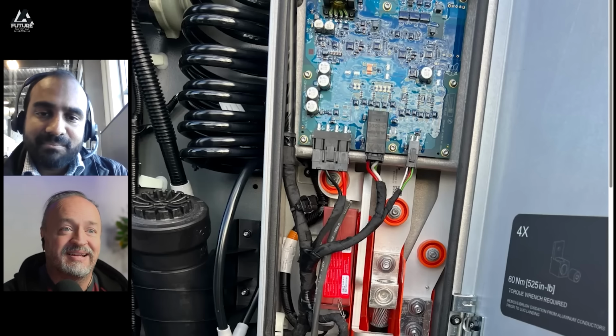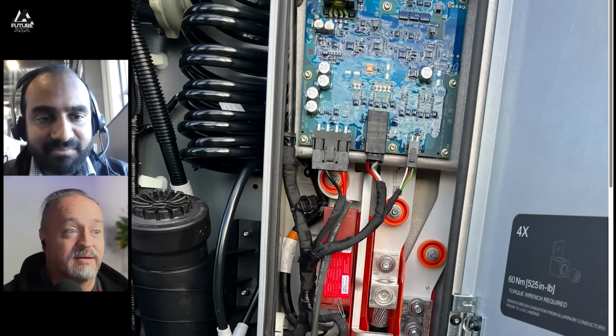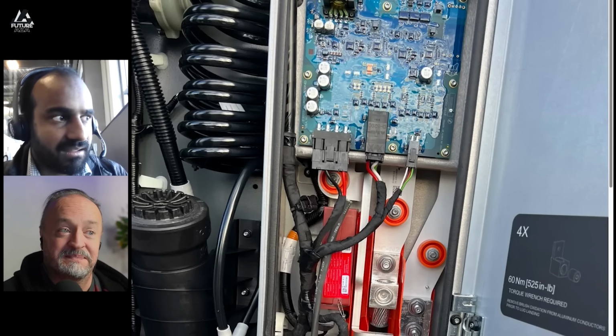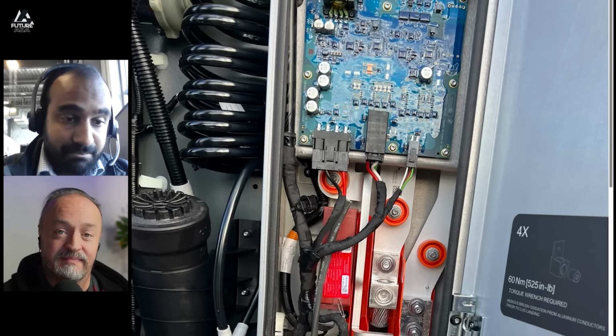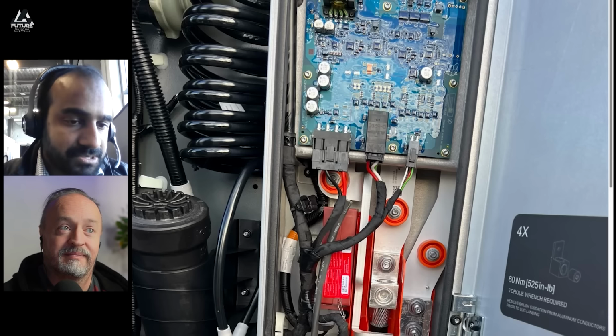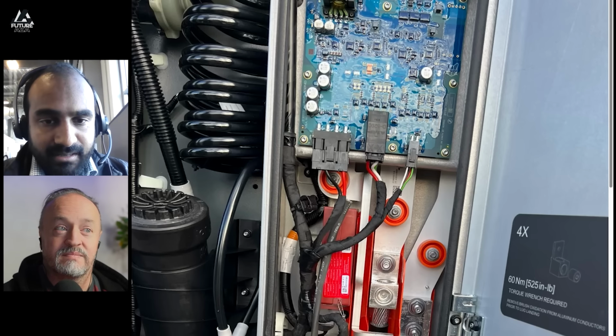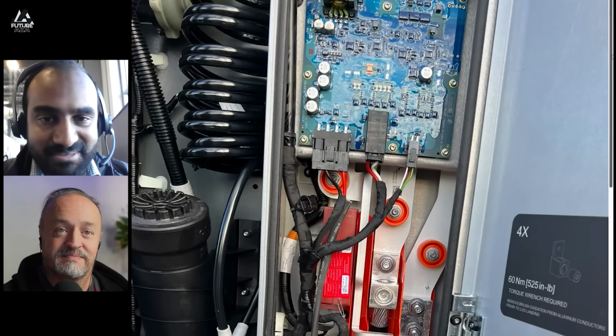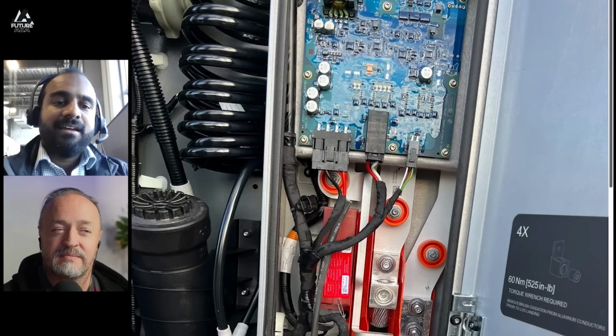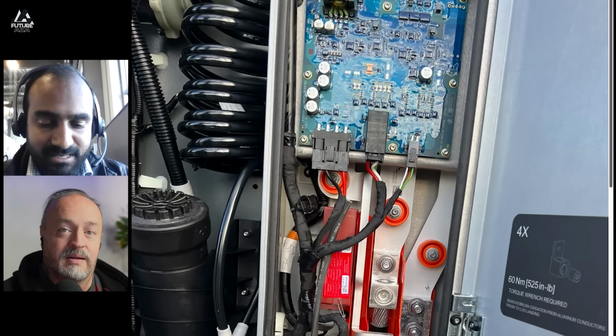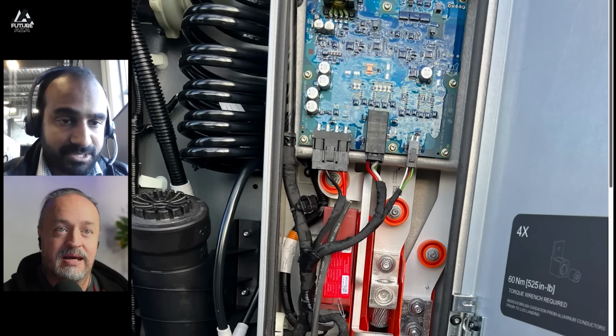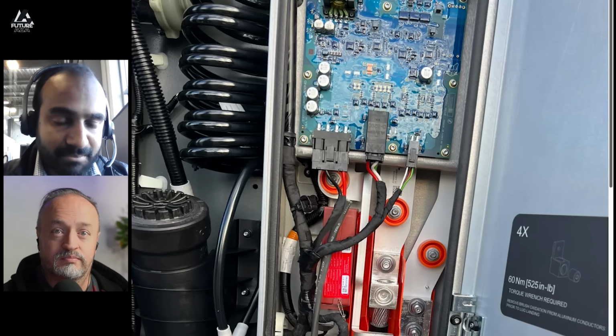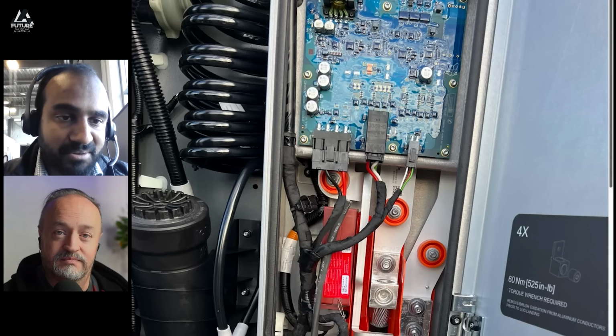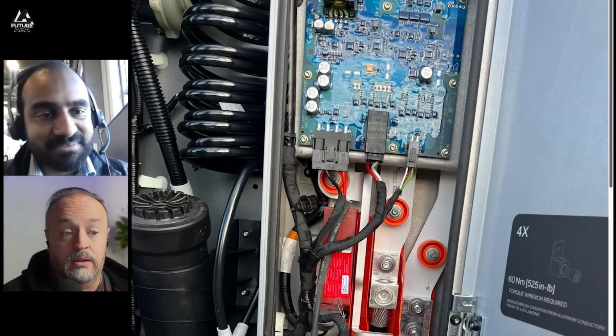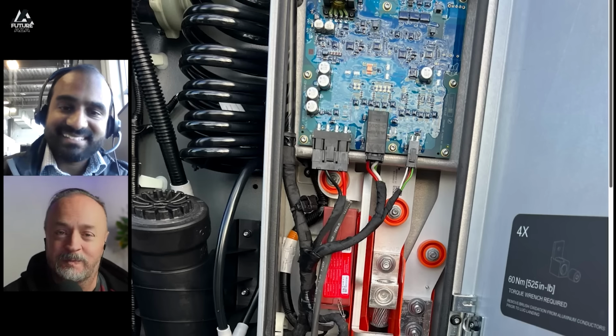On that board, there's another really important function that I don't think a lot of people generally appreciate when they're charging their electric cars, but it's one of the most important things a dispenser can do. I'm not 100% certain, but it's probably on that board somewhere. It's called insulation monitoring. This is really, really key because if you have a short between some current carrying portion of the cable and ground, you are effectively one fault away from electrocuting something and possibly someone. And insulation can break down, right?